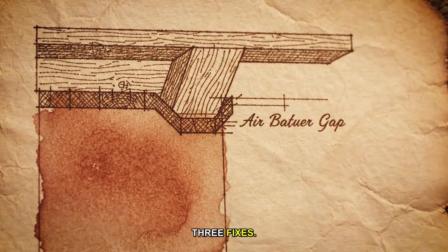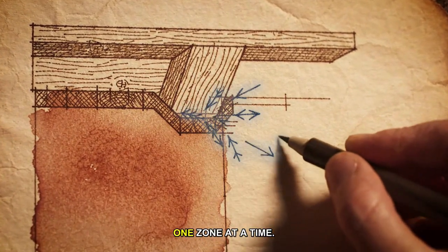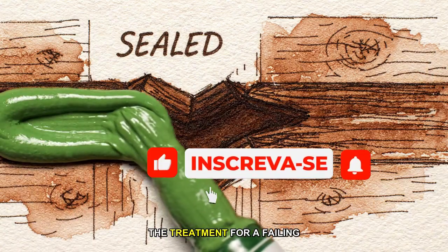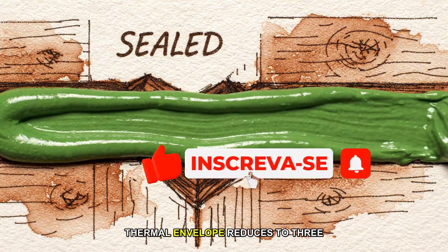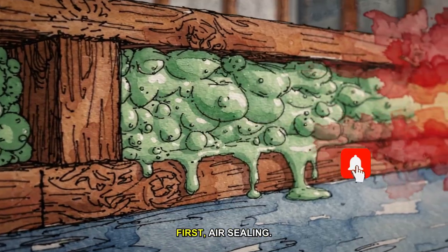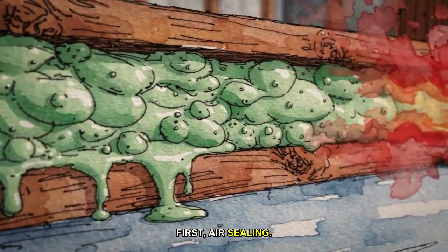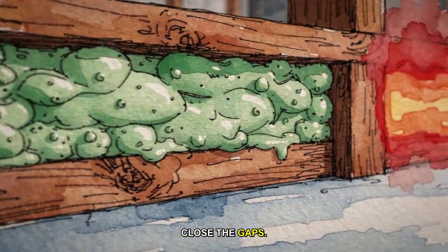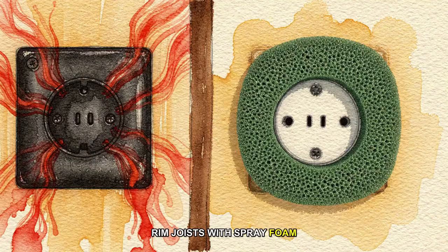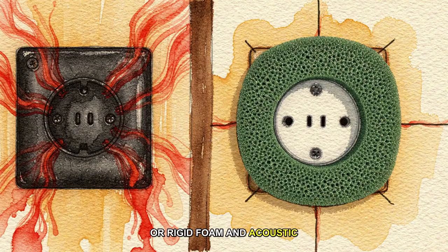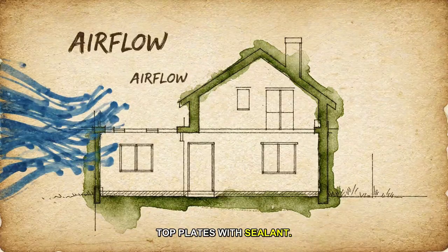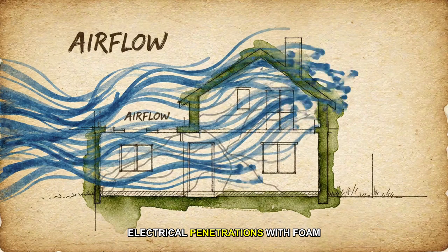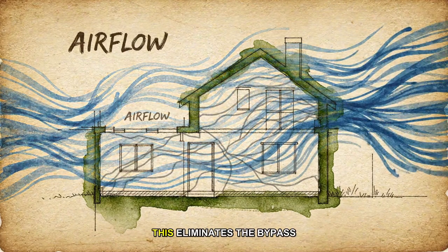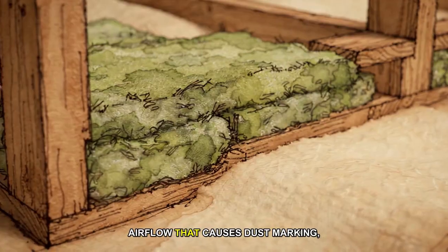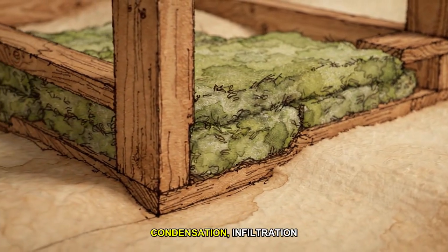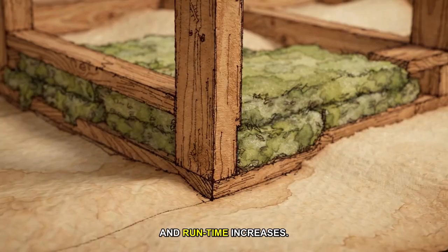3 fixes, all 5 symptoms, 1 zone at a time. The treatment for a failing thermal envelope reduces to 3 interventions. First, air sealing. Close the gaps. Rim joists with spray foam or rigid foam and acoustic sealant. Top plates with sealant. Electrical penetrations with foam backer and cover plate. This eliminates the bypass airflow that causes dust marking, condensation, infiltration losses, and runtime increases.